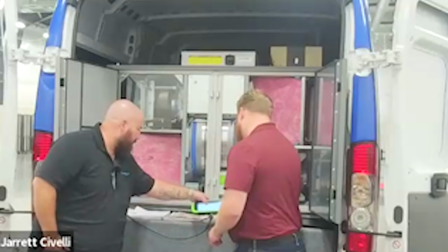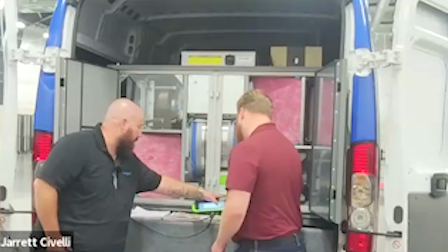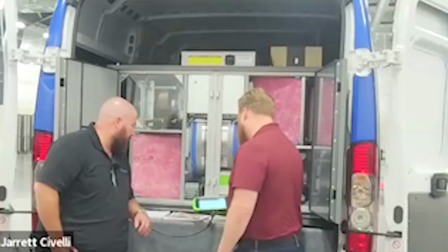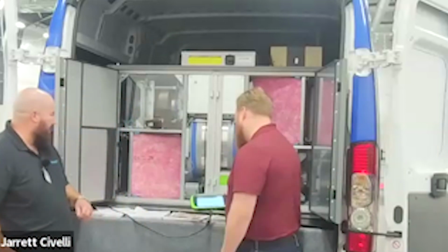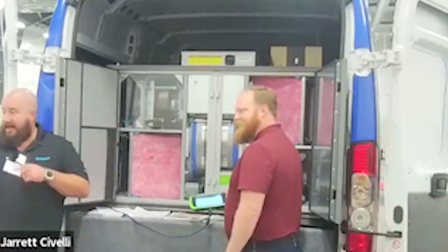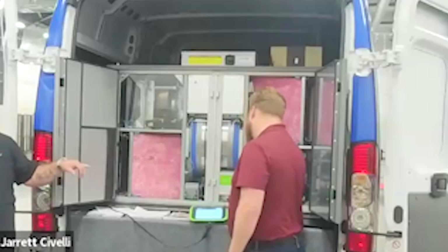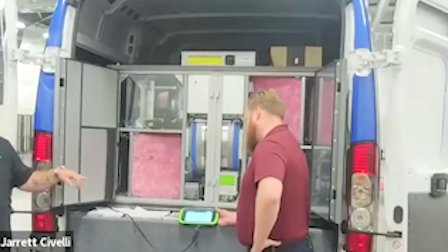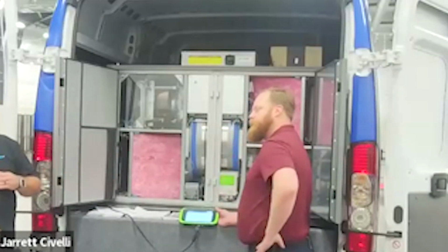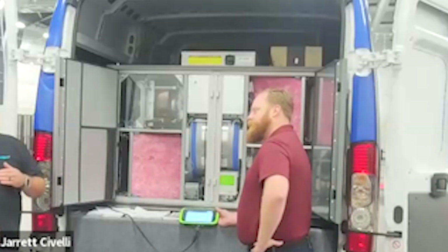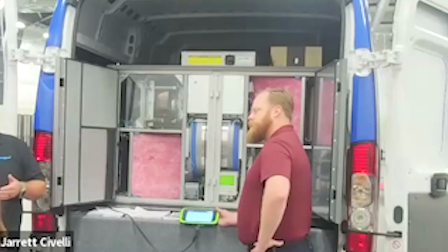Let's see if we can make it stop. Turn off—that's for when you have a wildfire outside, so it could pressurize the building. Correct, controller. One of the great things is you can set a percentage of differential on your extract versus your supply, or set it based on CFM. So if you're trying to maintain building pressure, it's just a matter of pushing a couple of buttons and hitting enter.